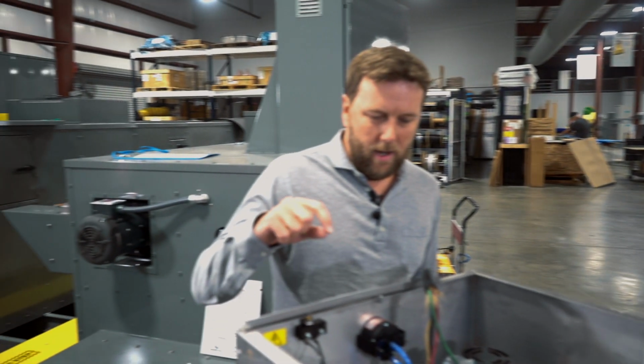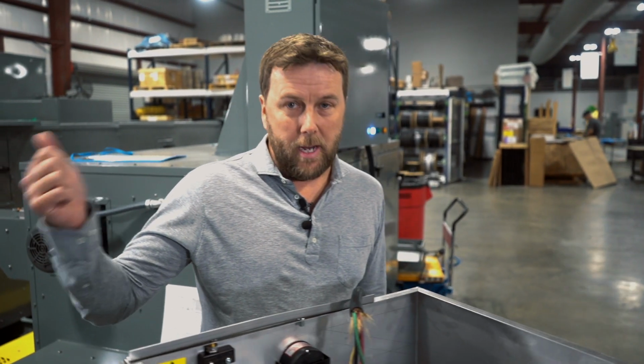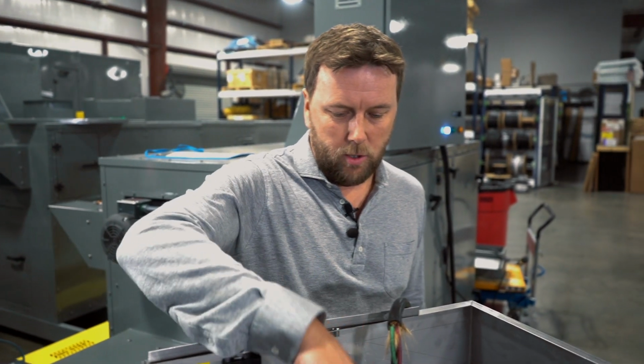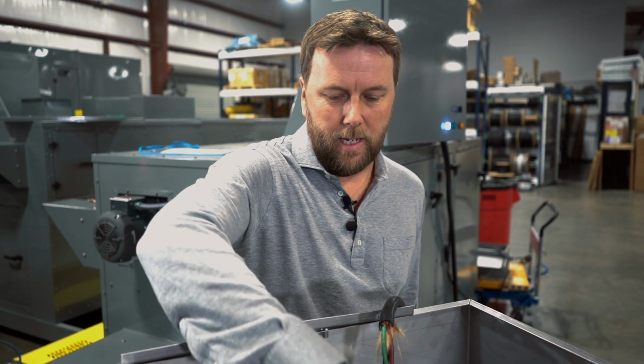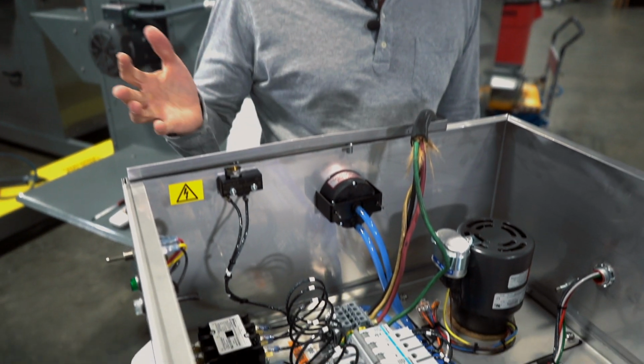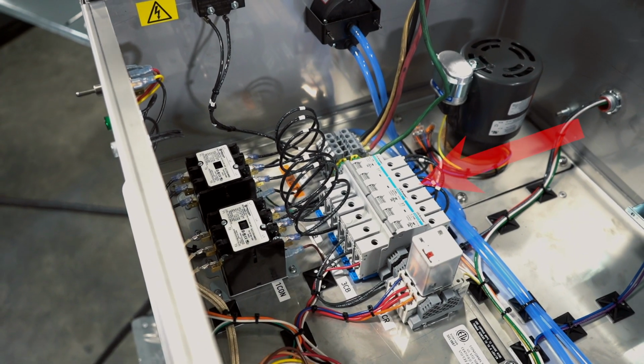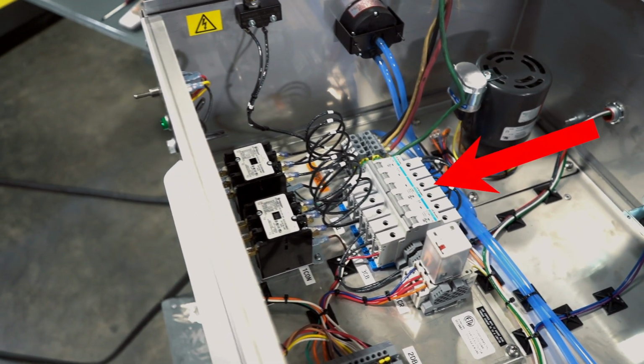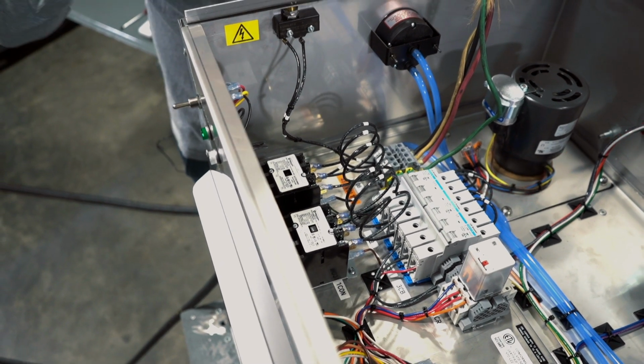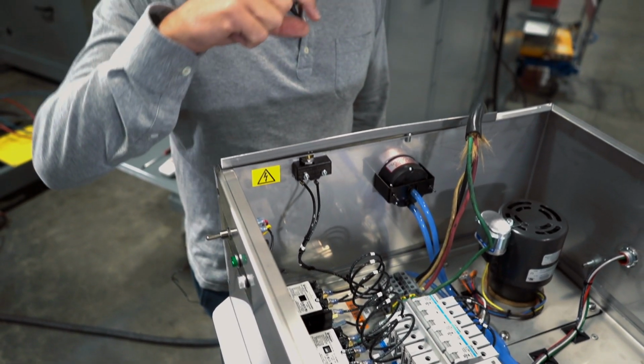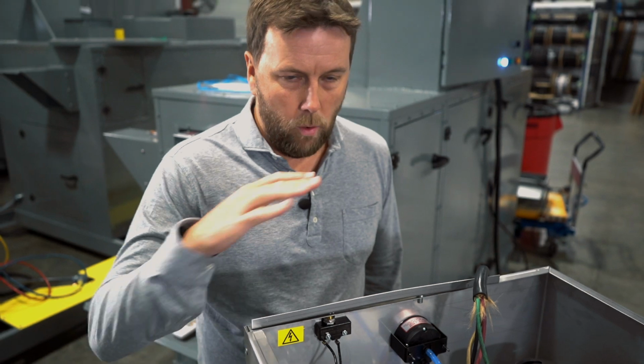One thing I should point out: before I throw the main breaker on, we always start with every one of the circuit breakers in the off position. The last thing we want to do is send power throughout the entire system all at once. So from a safety standpoint, we like to work systematically through the system one by one.